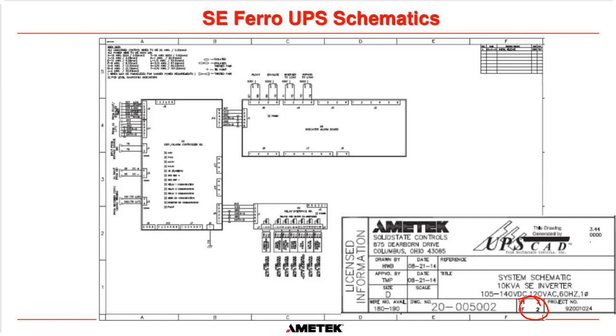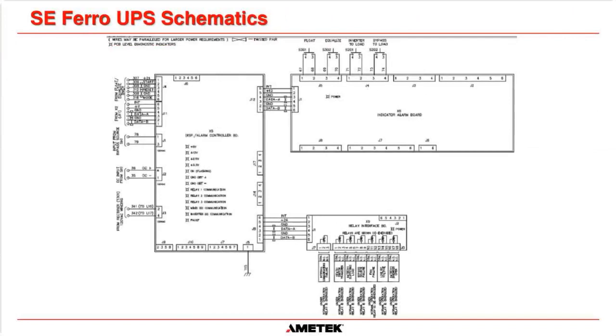And then page 2 of the inverter diagram tells us about the control boards, and we'll just zoom in on this. X5 is a display alarm controller, and you've got all these LEDs on the board, and it tells you what each of the LEDs is and what it shows you. So all of these LEDs, the power supply LED should be lit. It's saying this one here should be okay and flashing. This is telling you if there's a ground fault positive, ground fault negative, so they should not be lit in normal operation. These are communication failure alarms with this relay interface board.